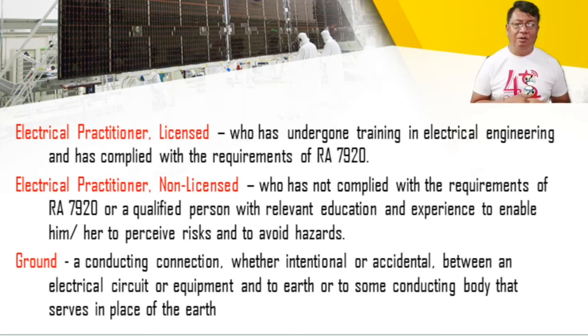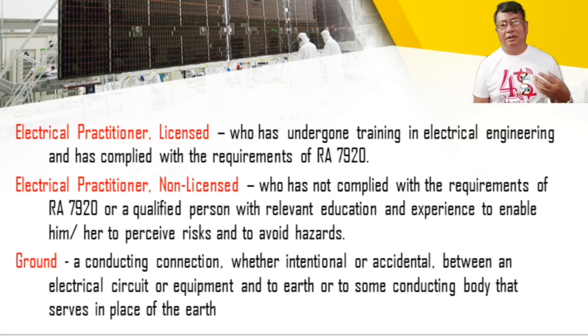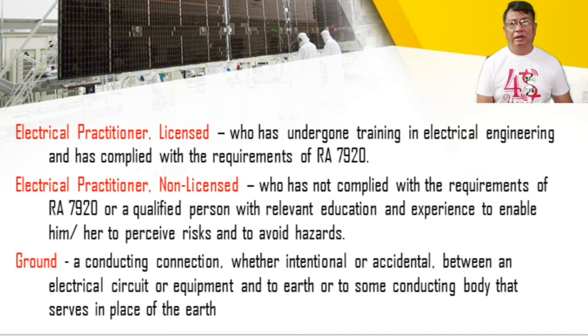Okay, sometimes some of us might give less attention to the grounding system. But of course, this is very dangerous because it might damage your installation if it is not grounded properly. So ground is a connection, whether intentional or accidental, between an electrical circuit or equipment and the earth or to some conducting body that serves in place of the earth. Okay, why earth? Because as we know, the best and most efficient grounding is towards the ground, which is earth, or through metals, which will be in place of earth also.